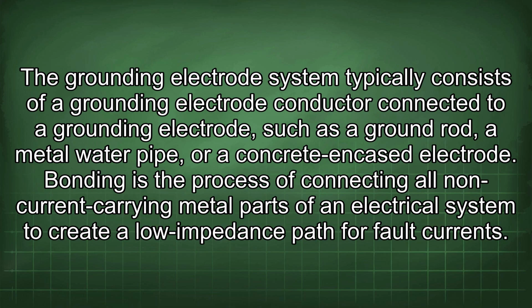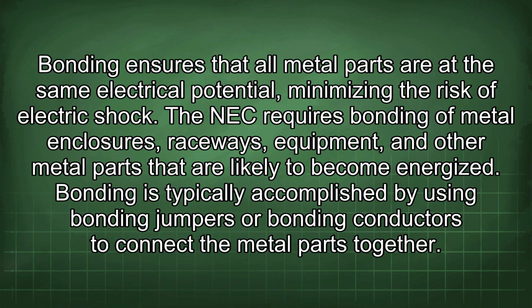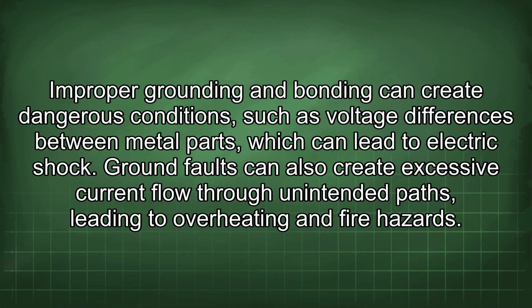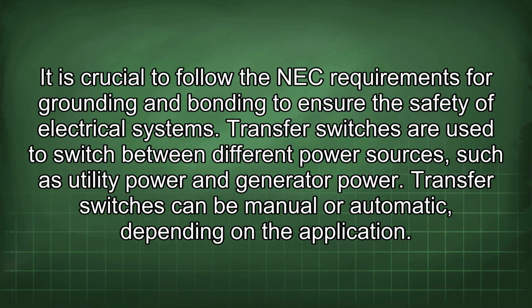Bonding is the process of connecting all non-current carrying metal parts of an electrical system to create a low impedance path for fault currents. Bonding ensures that all metal parts are at the same electrical potential, minimizing the risk of electric shock. The NEC requires bonding of metal enclosures, raceways, equipment, and other metal parts that are likely to become energized. Bonding is typically accomplished by using bonding jumpers or bonding conductors to connect the metal parts together. Improper grounding and bonding can create dangerous conditions, such as voltage differences between metal parts, which can lead to electric shock. Ground faults can also create excessive current flow through unintended paths, leading to overheating and fire hazards. It is crucial to follow the NEC requirements for grounding and bonding to ensure the safety of electrical systems.